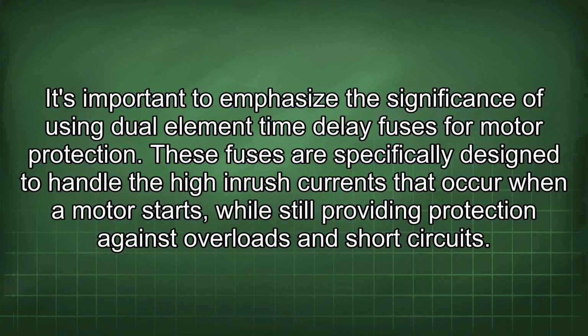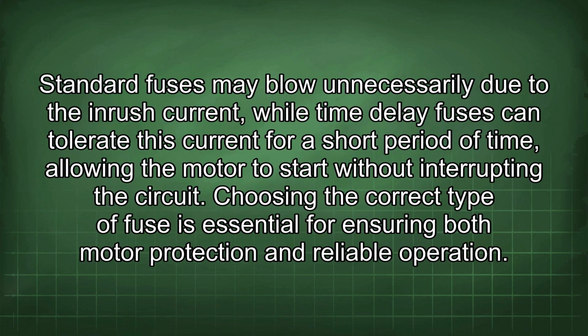It's important to emphasize the significance of using dual-element time delay fuses for motor protection. These fuses are specifically designed to handle the high inrush currents that occur when a motor starts, while still providing protection against overloads and short circuits. Standard fuses may blow unnecessarily due to the inrush current, while time delay fuses can tolerate this current for a short period of time, allowing the motor to start without interrupting the circuit. Choosing the correct type of fuse is essential for ensuring both motor protection and reliable operation.